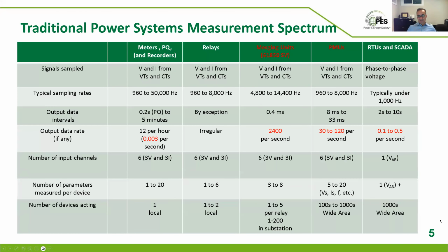Moving on, a little bit of a chart to remind people of the measurement domain in the traditional power system. Let's not worry about synchro waveforms per se, or the fastest traveling wave measurements, but just the regular power industry measurements to some extent. On the right-hand side, you have remote terminal units and SCADA type of information. SCADA used to be every 2 seconds, every 10 seconds, your RTU takes a measurement and sends it through your SCADA network to a control center. It may come from thousands of points on your grid. It's usually a phase A to B voltage or something equivalent of that. So it's very low resolution in terms of time, but it covers a very wide area, and data arrives at sometimes random times. You don't necessarily have good synchronization between data because they are not time tagged at the source.